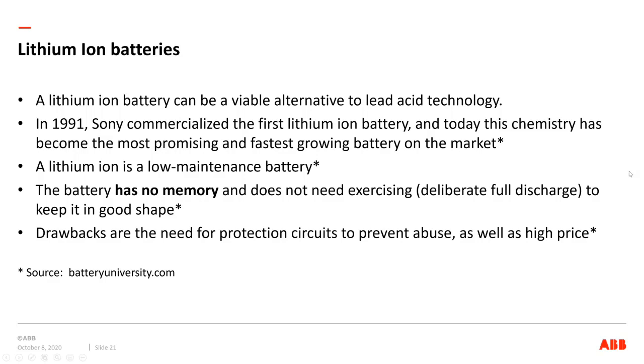They're very low maintenance. There's no gassing, which is an issue with all other types of batteries. They like to be cycled. They have high cycle life. And they don't have memory, which is an issue. Didn't talk about that, but that is an issue with lead acid batteries. If you repeat the same cycle, the battery kind of gets in that mode.